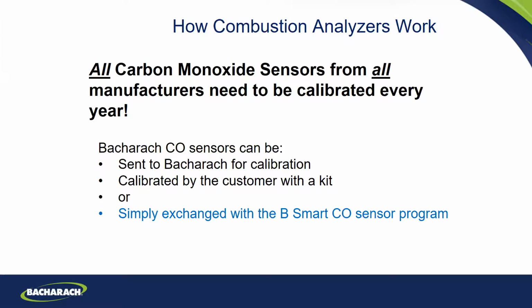You can buy a calibration kit. If you bought 15 units, maybe you would prefer to calibrate them yourself. The onus is now on your back, but we sell you a calibration kit. We'll show you how to do it in the manual. Take good notes, write down the serial numbers of the units and when you did it and how you calibrated, put it in your files. So if anything goes wrong, you have proof that you calibrated this and it works correctly.